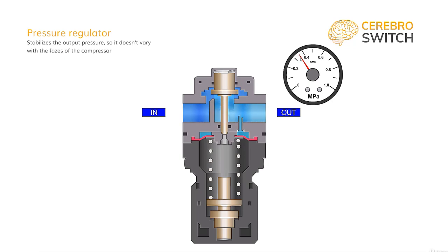the out port. If we take a look at the gauge, we'll observe the pressure stabilizes itself lower than the 0.4 megapascal setting. This is an indicator that for the pressure regulator to provide us with the needed setting, we must set it while the consumption is taking place, not at rest.